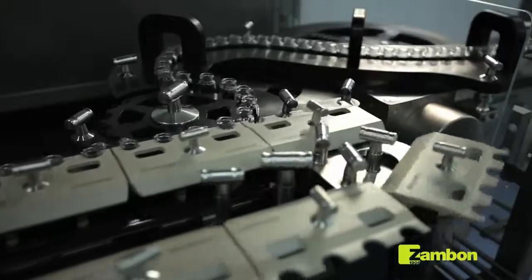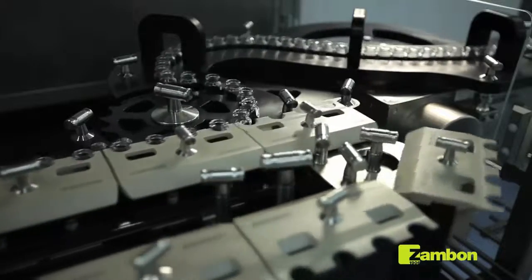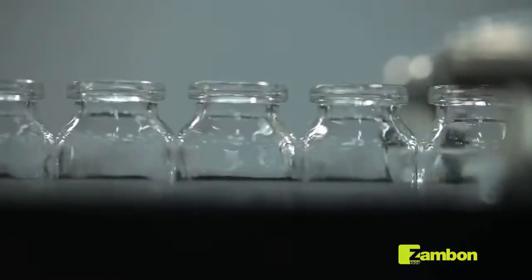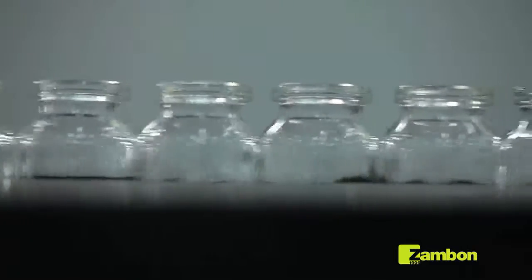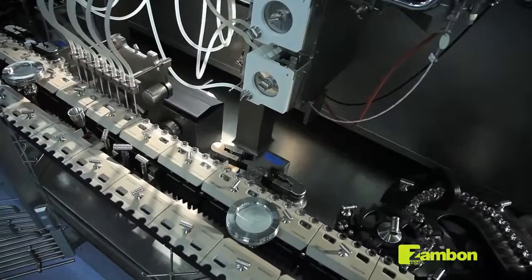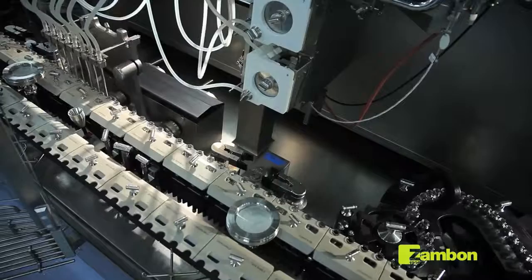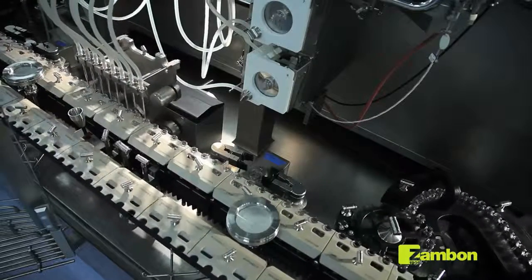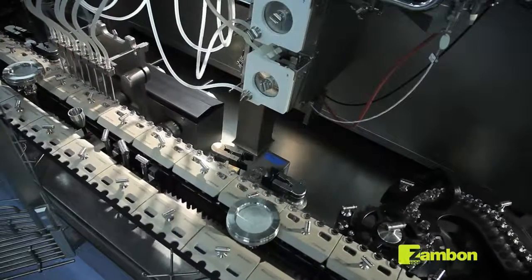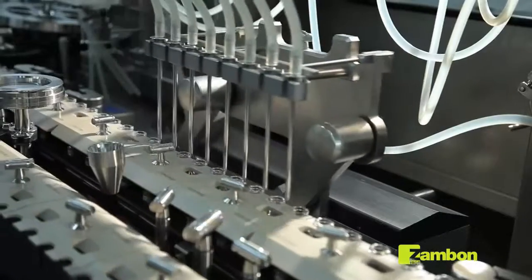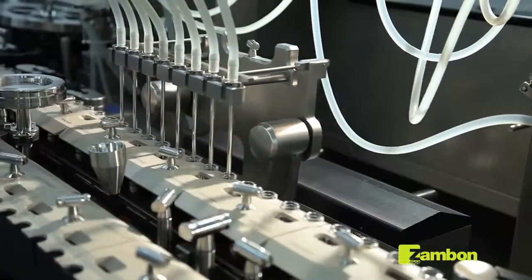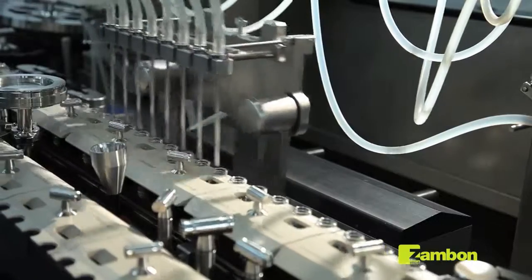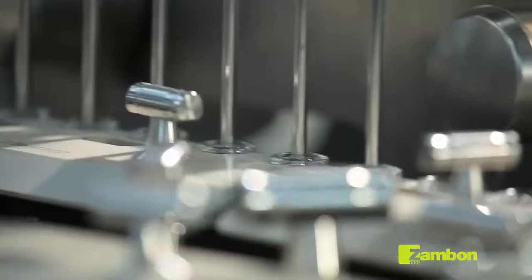The solution is taken automatically from the tank in the preparation room through a transfer line equipped with sterilizing filters. The bottles coming out of the sterilization tunnel are filled with a quantity of previously prepared solution through a series of needles. During the process, the weight of the solution is controlled continuously by means of an automatic weighing system.